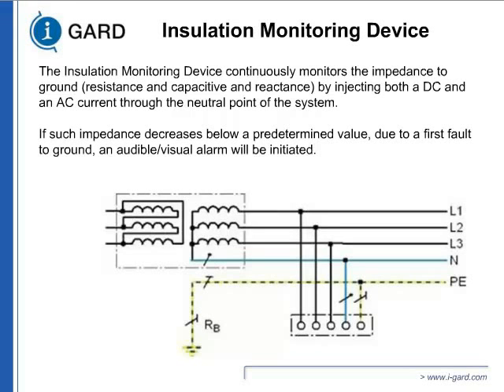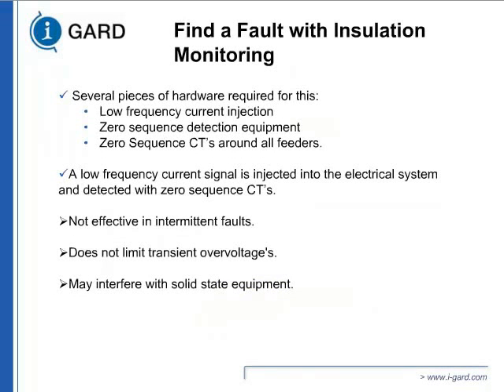With a planned outage, you could program what the insulation should be, and if it goes below a certain value, you sound an alarm. How do you do that? Since it doesn't have any ground fault path, you need a zero sequence CT, and you need to inject a very low voltage, low frequency current. That means when the insulation is damaged, you will have a current in the zero sequence CT. A zero sequence CT will show you zero if everything is balanced, and if there is some current flowing through it, it will give you a value.